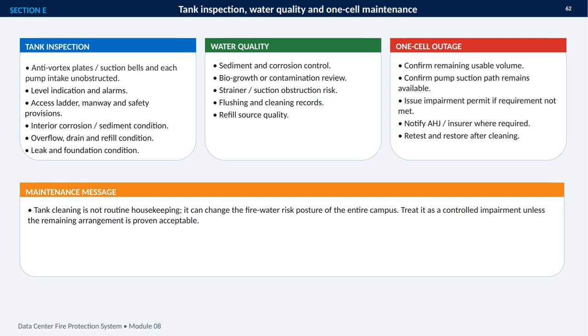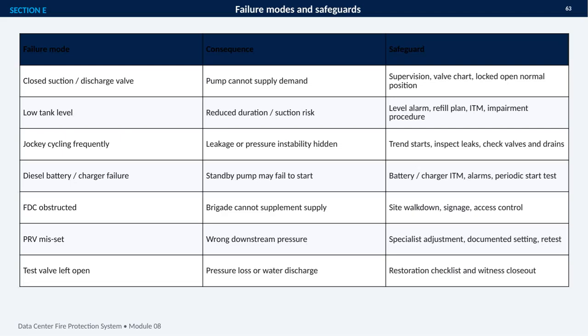Tank cleaning is a controlled fire protection impairment, not routine housekeeping, because it can change the risk posture of the entire campus. This section focuses on failure modes and the safeguards that prevent them from becoming serious protection system deficiencies. The key idea is that many failures are not dramatic equipment breakdowns. They are configuration, maintenance, or restoration problems that can quietly reduce system performance.